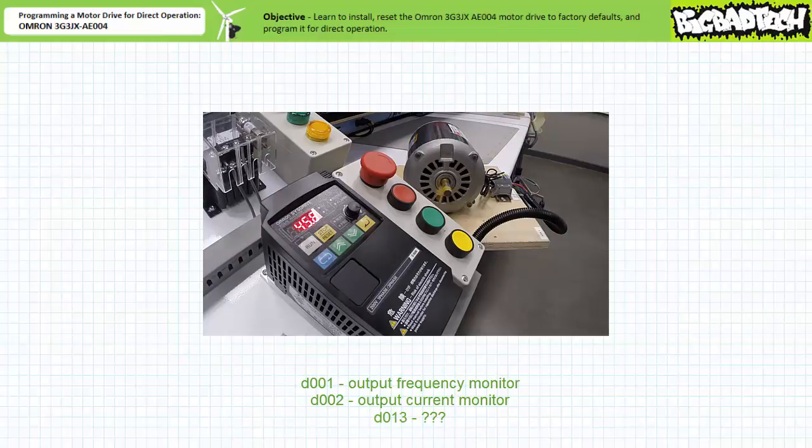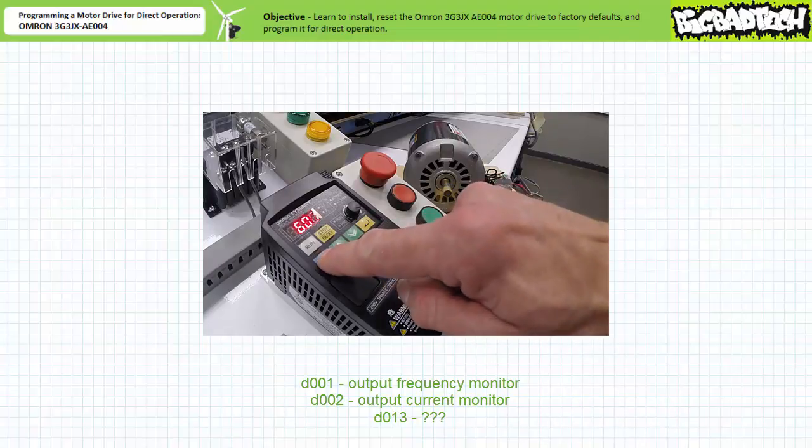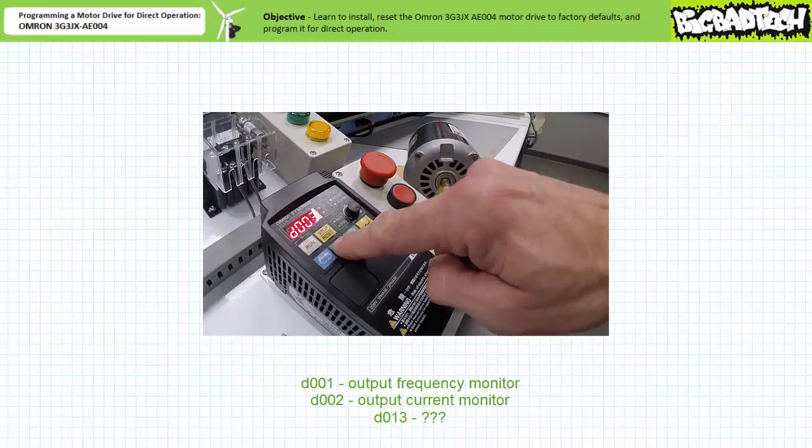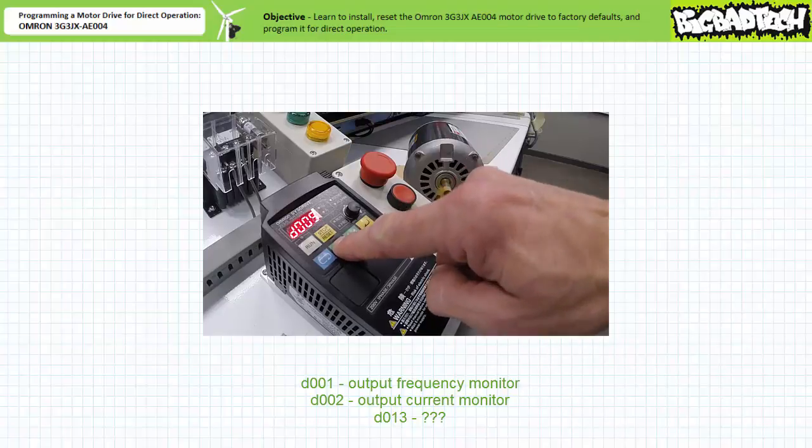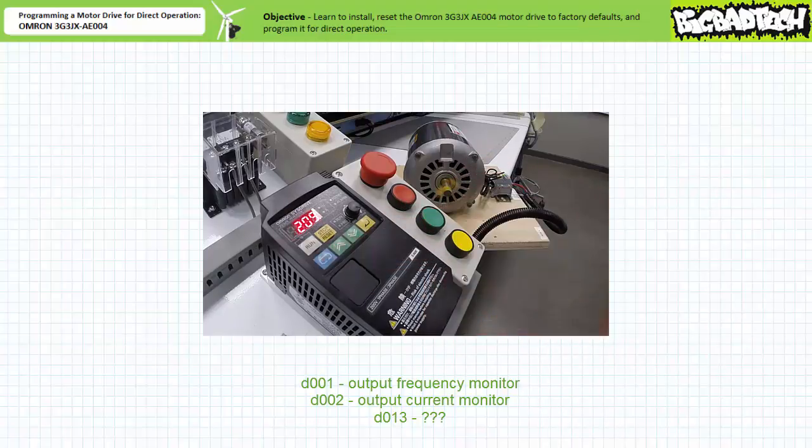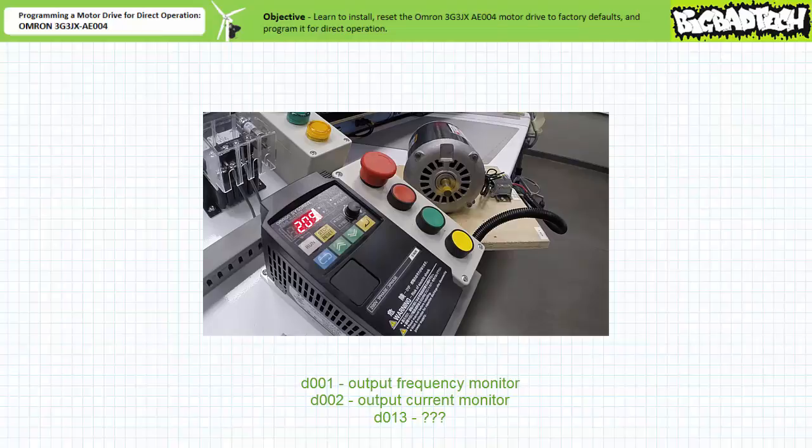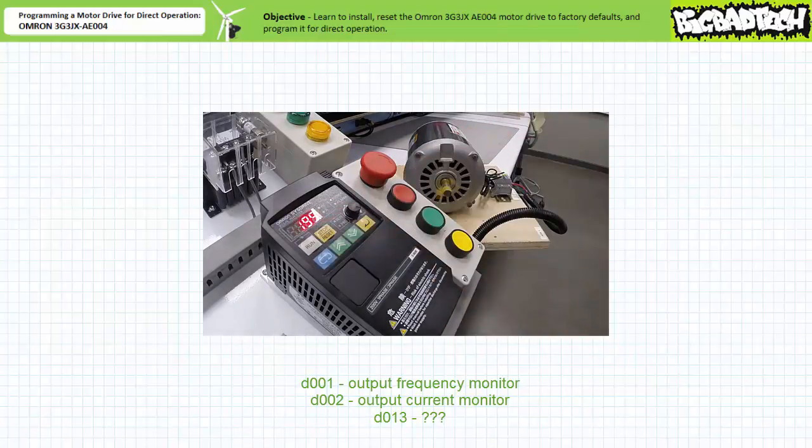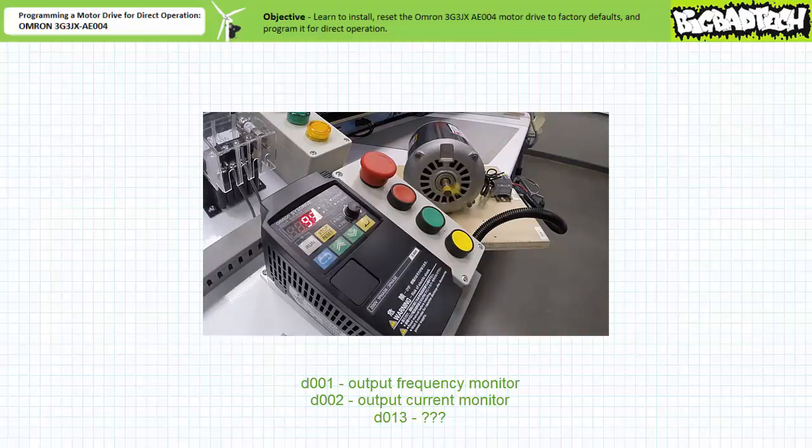The motor drive at 60 hertz, the motor stabilized at the no-load speed. The motor drive is saying 209. What does the data in parameter D013 mean? As a further challenge, consider the following behavior. When I press stop, the motor drive reduces excitation frequency. Note that the data in parameter D013 also decreases as the motor decelerates and comes to a rest.